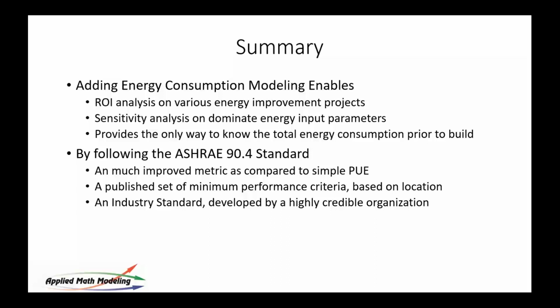Yeah, I could talk about this one for a while, but this is more about a simulation than it is about operation. However, in operation, I think it's important to monitor inlet and outlet temperatures of the racks at different heights, so you have rack level temperature data. And I think that working to add whatever you can to the building management system in terms of trending reports and things like that, that can better utilize what you've already got installed for monitoring, and additional monitoring on pieces of equipment that aren't currently being monitored, are the main general areas where I'd focus.